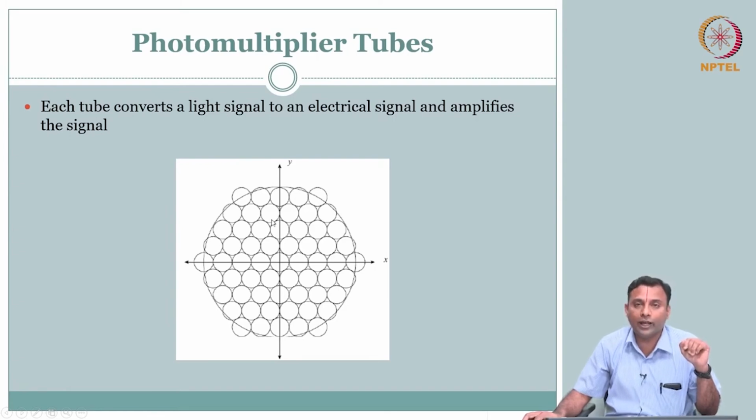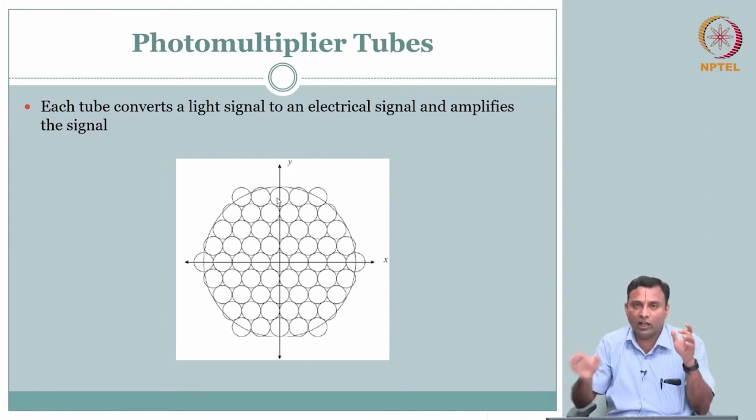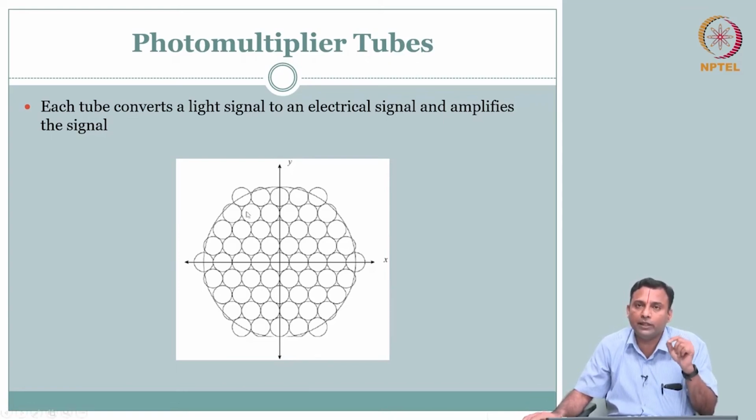So depending on the location where the light comes out, more of it will enter the nearest photomultiplier tube. The photons going to the side can enter the others as well, but the majority will enter along the line of sight, along the collimator and crystal. The objective of the photomultiplier tube is to convert these light photons into an electrical quantity. Now we will see what this photomultiplier tube is.